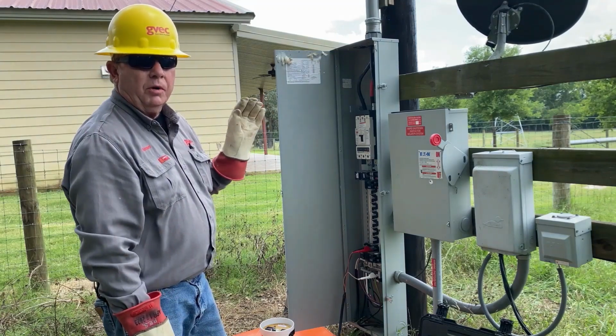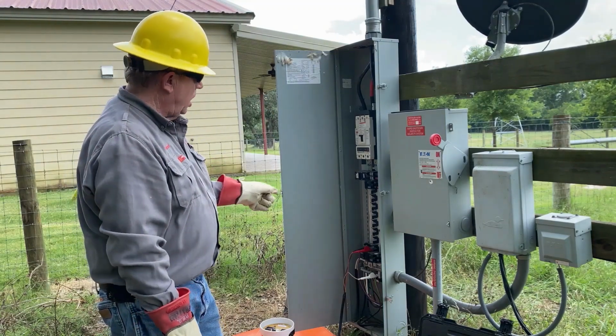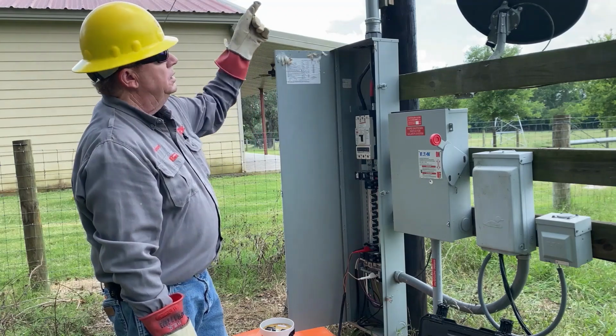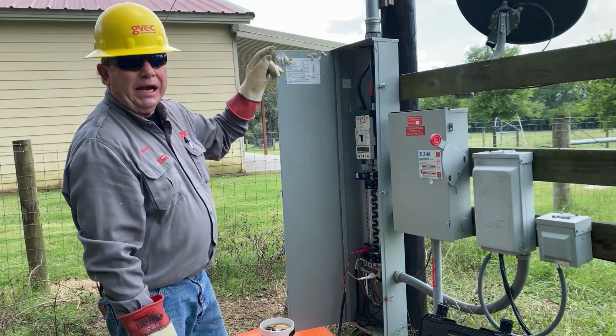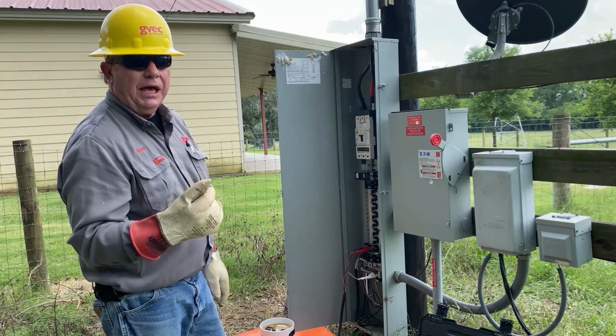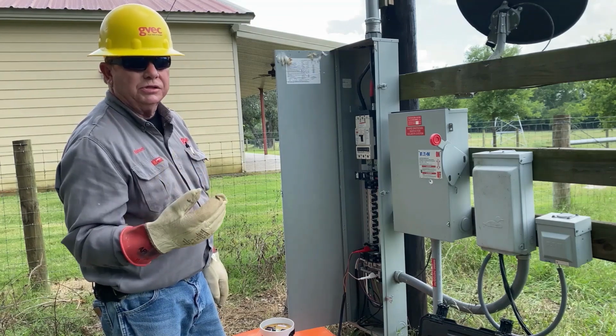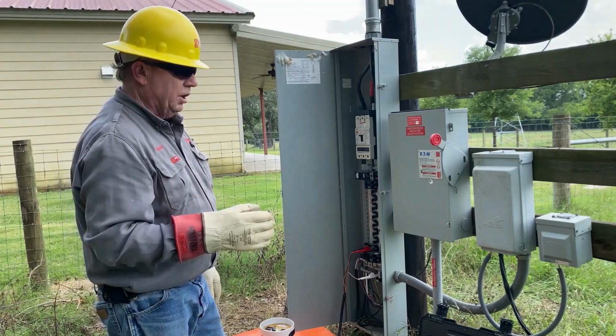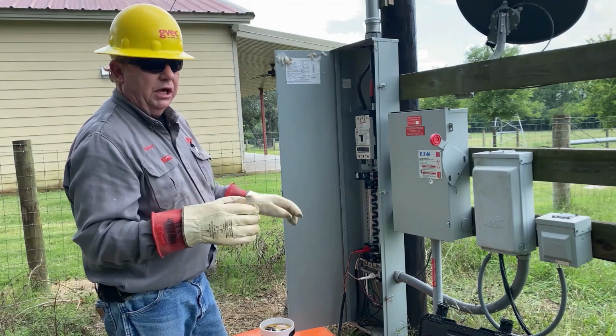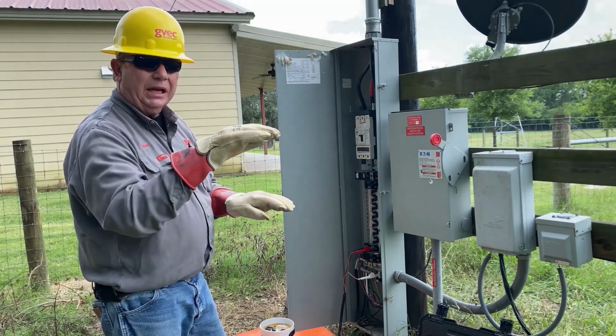We're pushing 23 amps back to the transformer on the neutral bus bar, through his riser, back on that triplex, and back to the transformer. The triplex, the transformer, and our connectors are all fairly new. So we're looking for the loss that caused this neutral unbalance.